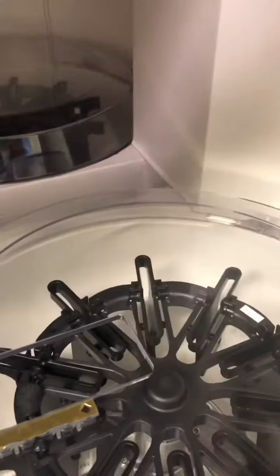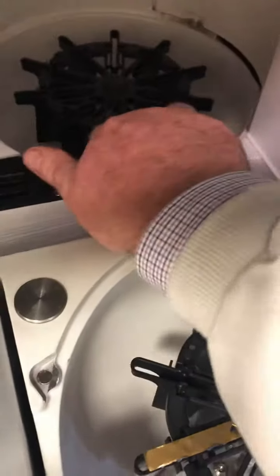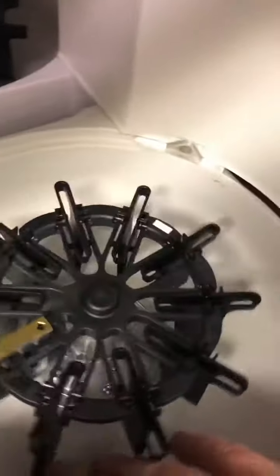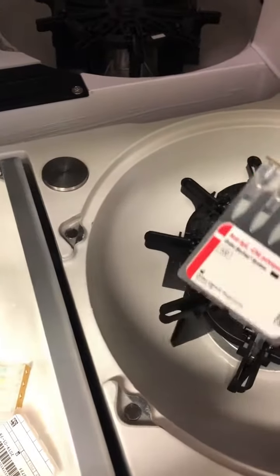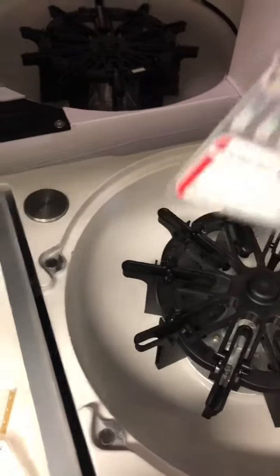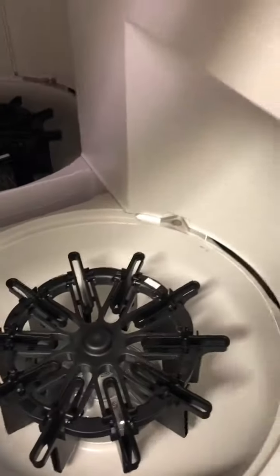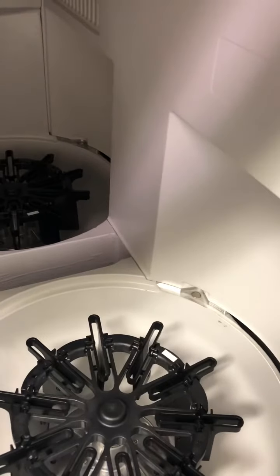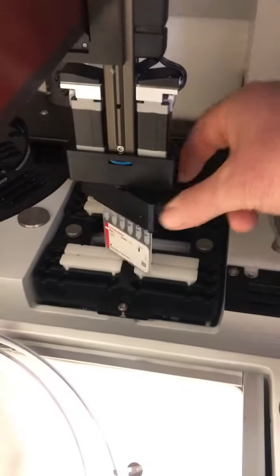The next thing I'm going to check is my centrifuge. I'm just going to remove the lids here. And I'm going to check that the centrifuges are free to move, which they are. I'm going to check for dropped cards underneath here, which there aren't, and that's clear as well. Now you notice that there's a card here. Now this may be causing an obstruction, I don't know, but I'm going to remove it because the instrument's going to remove it anyway. Okay, so the next thing I'm going to check is my gripper, and it's free to move, and as you can see here, this is certainly free to move.